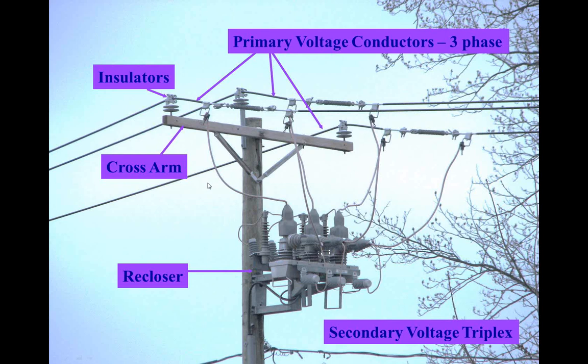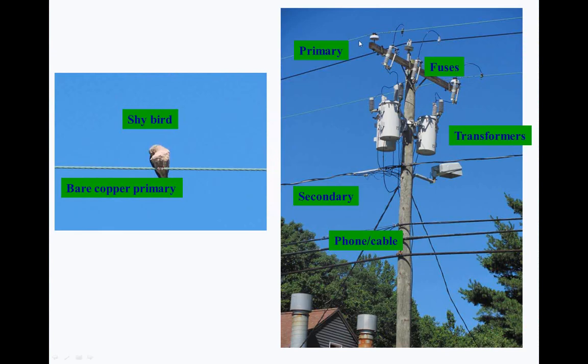Now, below the recloser, there's your primary voltage up on the top. That's the primary zone. Down below, all of our devices that connect to primary are above the secondary. The secondary is always the same, two legs of 120, and that's where the neutrals are. And we're going to make it a little more complicated. Here's our three-phase primary up there. I've got a bank of three transformers. When you see a bank of three transformers, we're making 277/480. And there's your secondary. Below that is phone and cable.